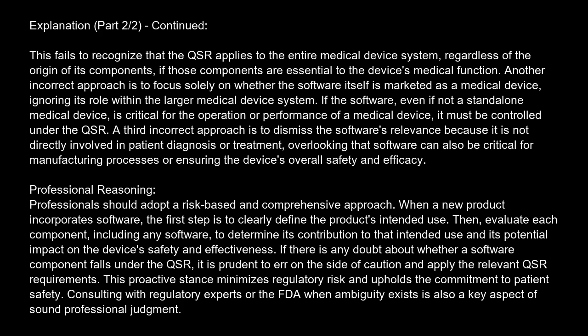Another incorrect approach is to focus solely on whether the software itself is marketed as a medical device, ignoring its role within the larger medical device system. If the software, even if not a standalone medical device, is critical for the operation or performance of a medical device, it must be controlled under the QSR.